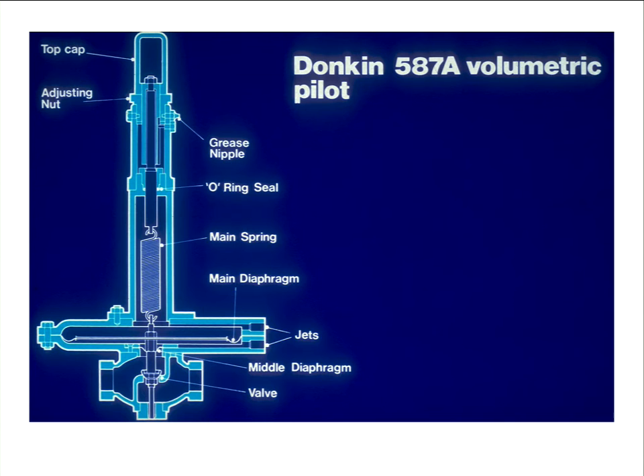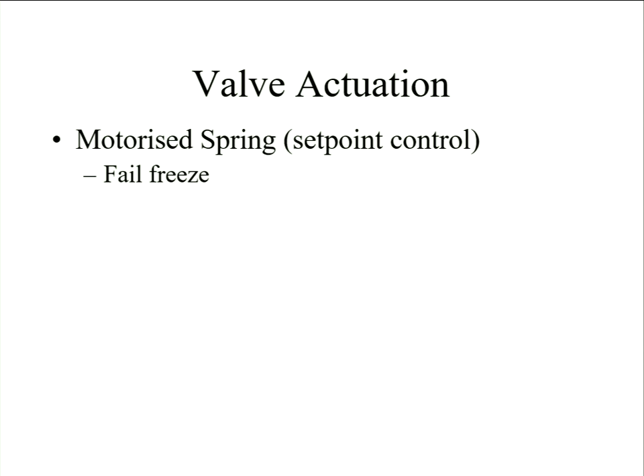You can start to gas load onto the diaphragms. If you remember when we used that diagram, there's a force balance here. If you start gas loading on that diaphragm, you're having the same effect as changing that spring setting and changing the forces on there to open that valve. So you can achieve a form of remote set point control, if that's what you need. Across the vast majority of the UK gas distribution system, you don't need to change things. You don't overcomplicate and put more process plant in than is necessary.